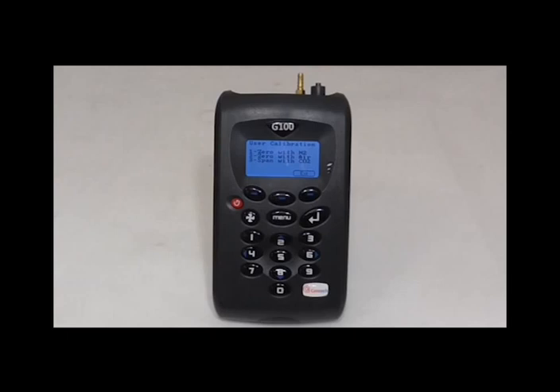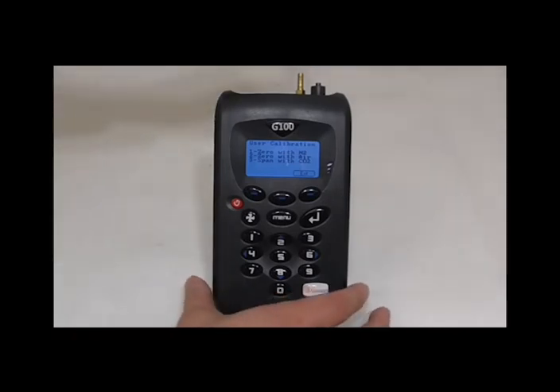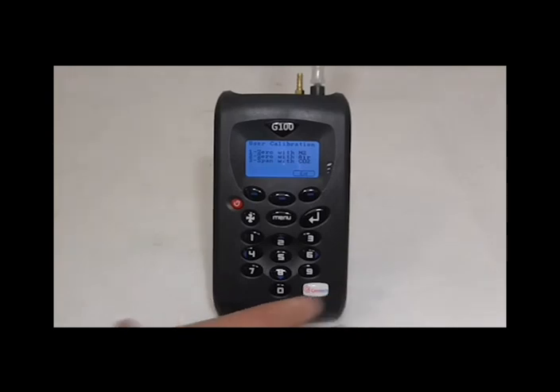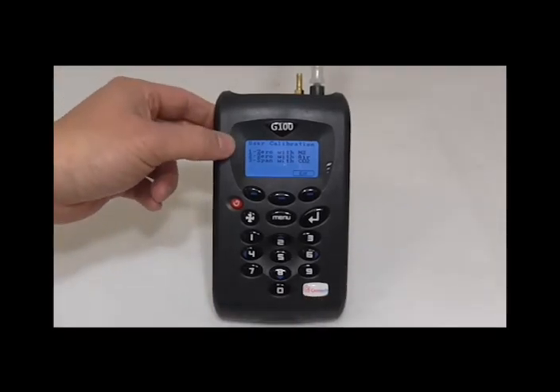However, we are aware that not everyone has access to this, so we will need to assess which filters you have. If you are using the Soda Lime filter, select the zero with N2 option. If you just have the PTFE filter, select the zero with air option. For this video, I have attached a Soda Lime filter by attaching it to the inlet port and twisting it clockwise. After it is attached, start the pump and let the instrument sit for 5 minutes.